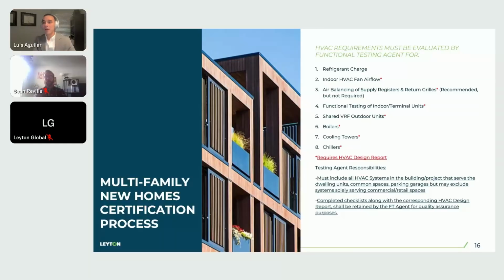So a lot of Energy Star compliance is making sure that things are operating how they're intended to operate, essentially, right? It's very important to ensure that an engineer has designed a certain property to operate at a certain amount of efficiency. However, we know that's not always the case on site, and when we go and test the equipment, it's not operating how it's supposed to be.